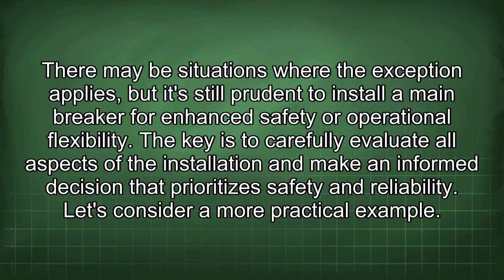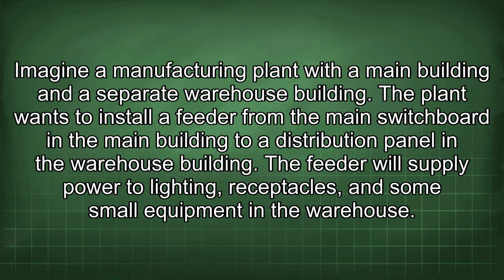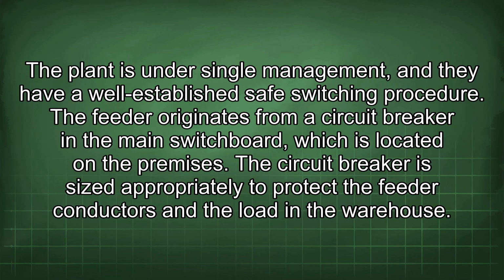Let's consider a more practical example. Imagine a manufacturing plant with a main building and a separate warehouse building. The plant wants to install a feeder from the main switchboard in the main building to a distribution panel in the warehouse building. The feeder will supply power to lighting, receptacles, and some small equipment in the warehouse. The plant is under single management, and they have a well-established safe switching procedure. The feeder originates from a circuit breaker in the main switchboard, which is located on the premises. The circuit breaker is sized appropriately to protect the feeder conductors and the load in the warehouse.